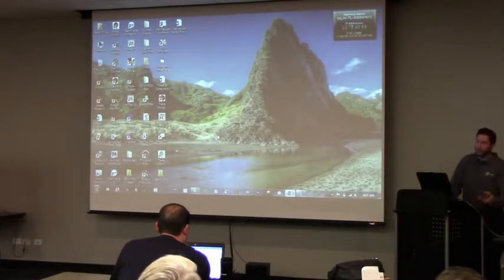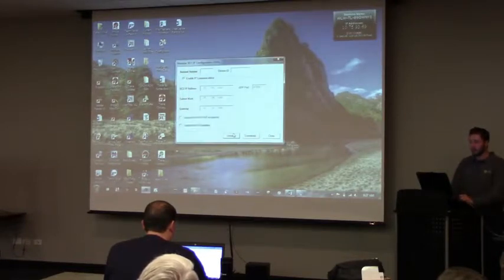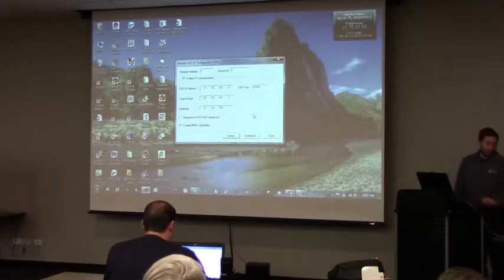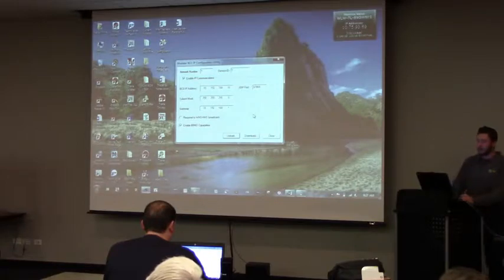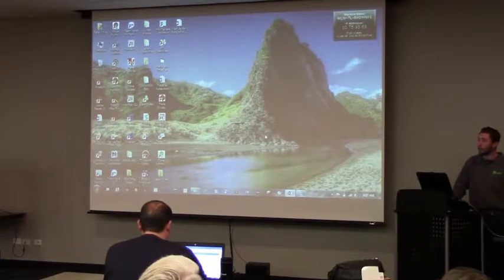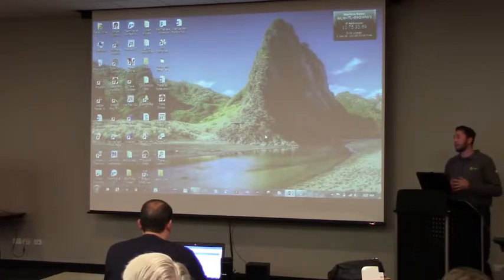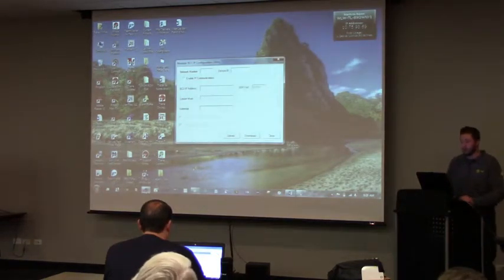So I got all the cables connected, my port set up and everything, so now I could actually go under the BCU config and just try and do an upload and see what's actually in there. I'm just going to put this to port 2 because that's where my port 2 is. So this is actually what's inside this BCU right now. It is network number 1, device ID 1, and then you have that IP address, and the BBMD is enabled. So if you wanted to, you could change your dip switches, and then make it 128, and then download it into there, and get all your addresses to what you need. Because it starts at 128 for your bridges, so you go to 129, 130, 131, and so on.